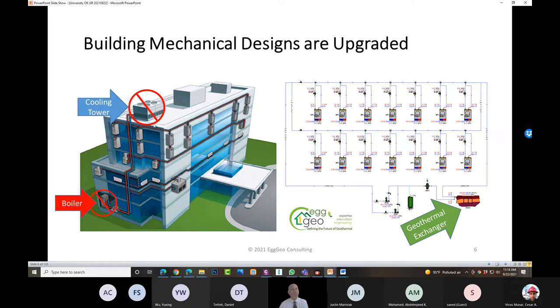And it uses a cooling tower to expel the heat in the summertime, and it uses a boiler to create heat in the wintertime. With a geothermal building exactly like this, these same heat pumps, which are represented in this hydronic schematic, use not a cooling tower and not a boiler.